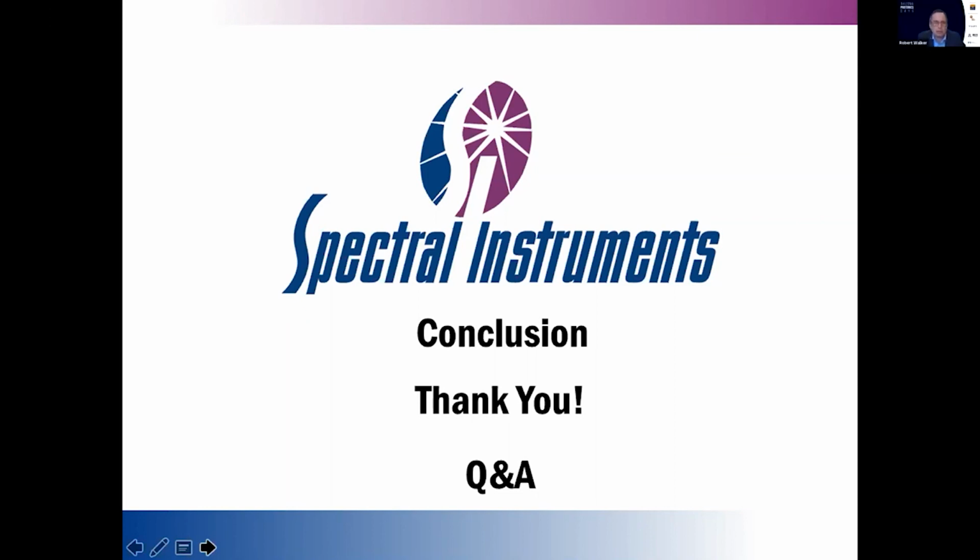Okay, thank you. Another question: how deep a vacuum can the RVT-100 be used in? Well, as I said earlier, it's really targeted to that 10 to the -6 vacuum range. If you do go lower than that, there's going to be outgassing, and you really can't get around that, because you can't bake the camera above about 100 degrees C. So there will be water coming off, but not much more than water. It did go through some rigorous testing at the NIF facility. They're very particular about what goes inside their target chamber. They can't afford to have things come off of equipment inside the chamber and deposit somewhere else where it isn't intended to go.